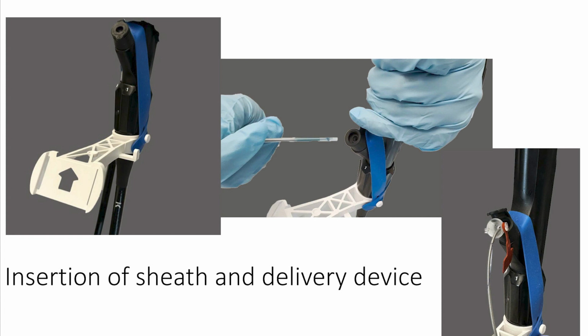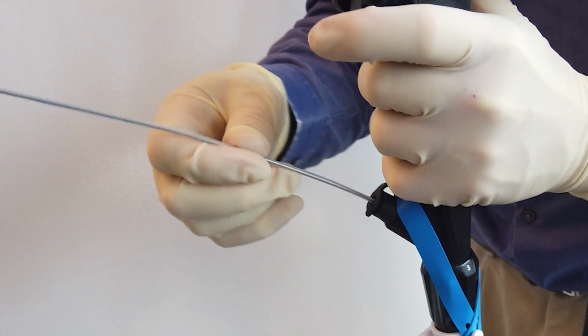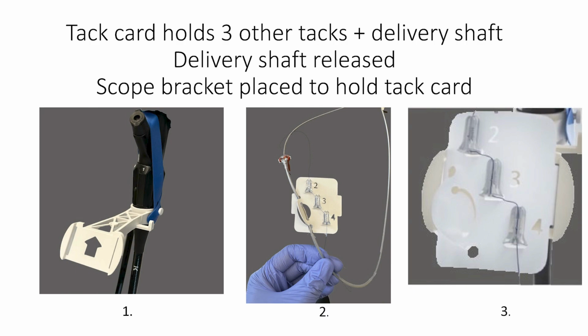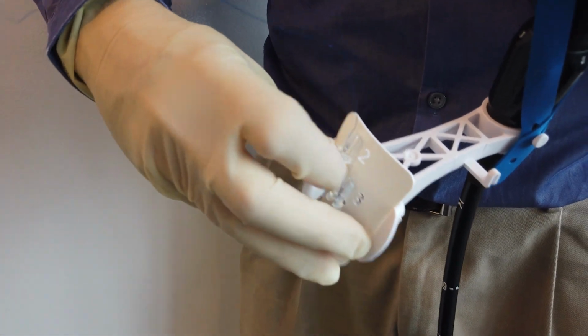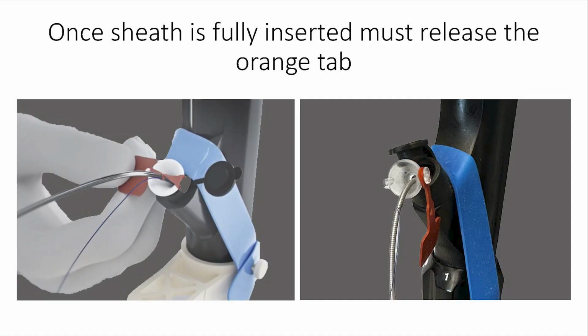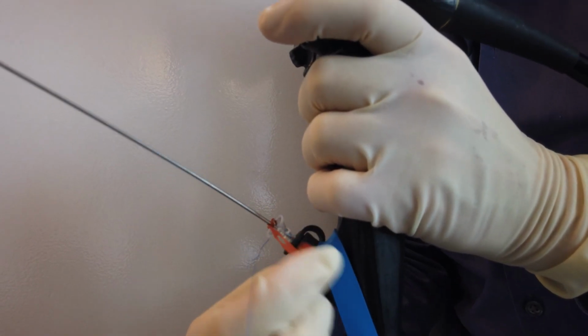After a plastic bracket that comes with the kit is mounted on the scope handle, the plastic sleeve and delivery device are inserted through the instrument channel. Next, the tack card must be mounted on the scope bracket. Prior to card placement, the distal shaft of the delivery device must be released from the card, which is then easily snapped into the bracket. The plastic sleeve is fully inserted until the flange at the end of the sheath sits inside the working channel's rubber cap. Next, the orange elastic band that stabilizes the delivery device is removed by pulling on the protruding rectangular tab. Once released, the delivery device can be further inserted.